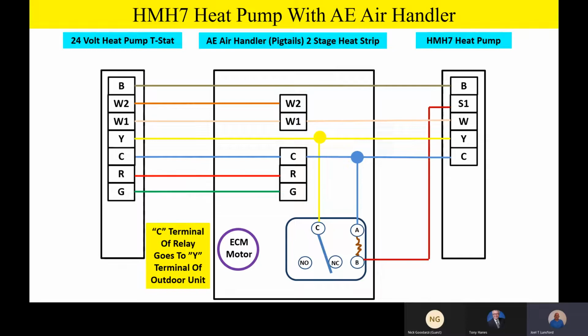C, or the common of the switching terminals themselves, will tie into your yellow wire going outside for your compressor call. So anytime we're calling for compressor operation, we're going to energize or have power on that common switching terminal or that relay terminal point.